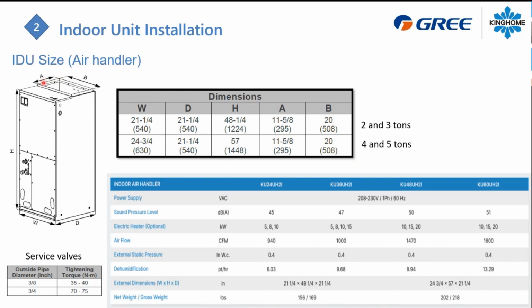Also, make sure that you know exactly the dimension for your duct, the supply duct that will match the A and B distance right here. The thing is, in this type of air handler, the top panel right here needs to be accessible for servicing or to make an easier installation when you're in the field. So if you are about to install some kind of air handler, just be aware that the first part of your ductwork must match this dimension here to make an easier access for the top panel right here.